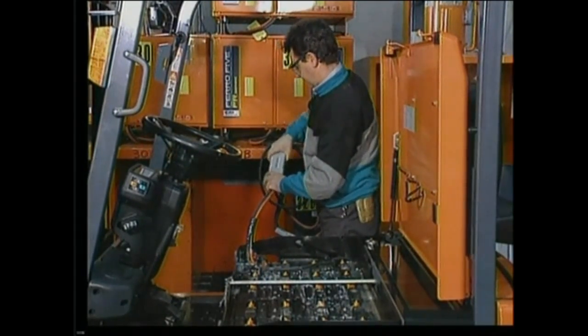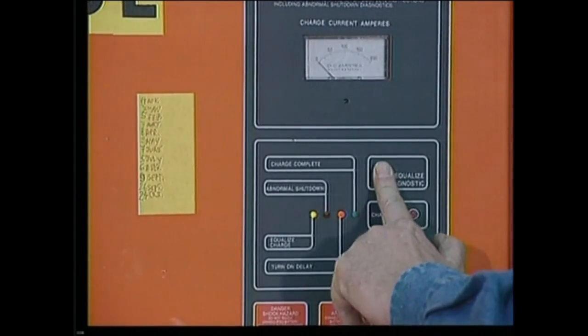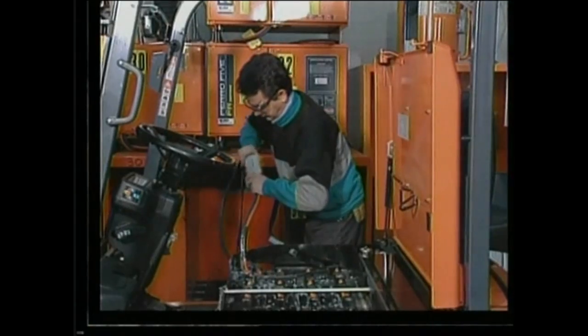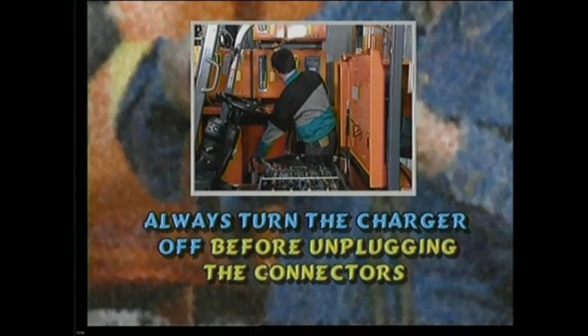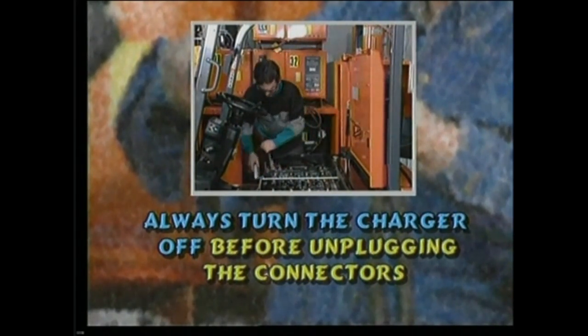Now connect the charger to the truck. Check the cables for wear and the connectors for damage. Turn on the charger following the manufacturer's instructions. When the charging process is complete, always turn the charger off before unplugging the connectors.